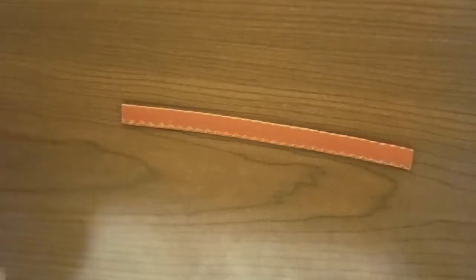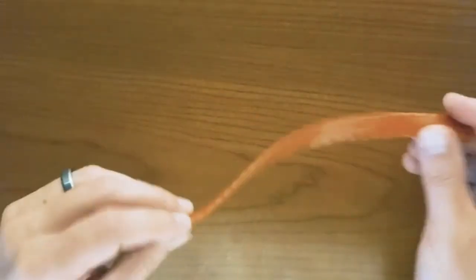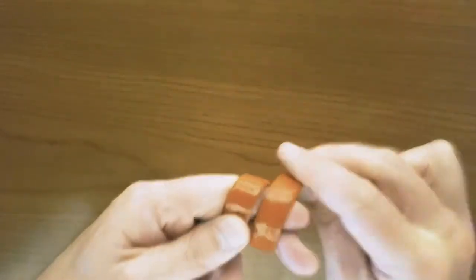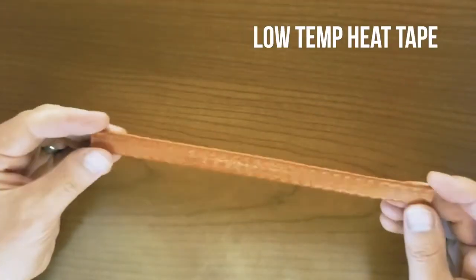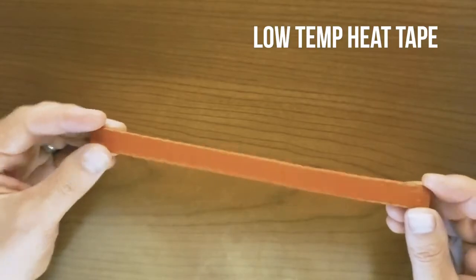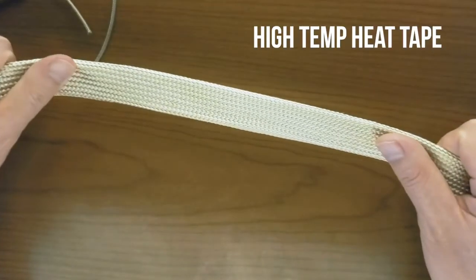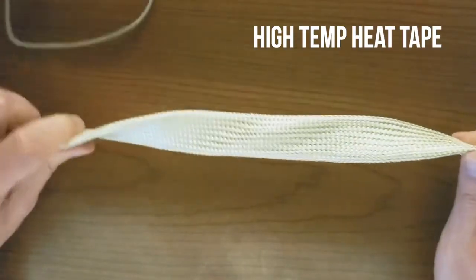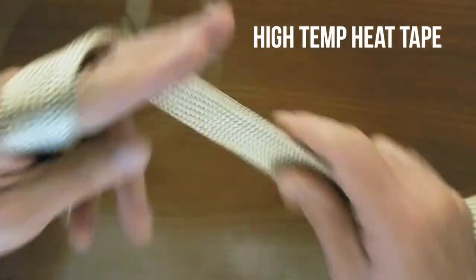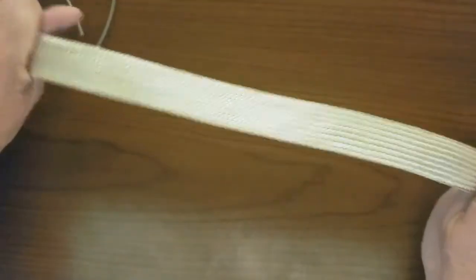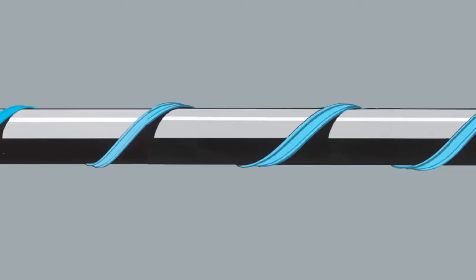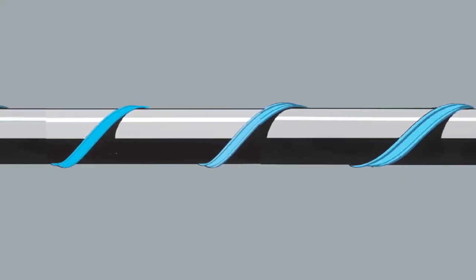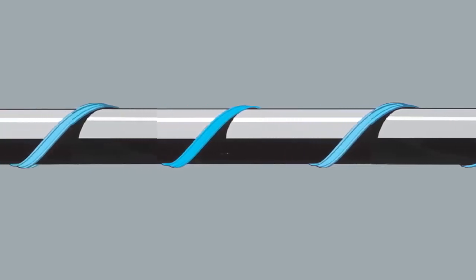Heat tape is a constant wattage resistive product that creates heat and is mainly used on small diameter pipes. Here's an example. It's small and thin and has two main varieties, the silicone one, which is used in low temperature applications below 400 degrees Fahrenheit, and the higher temperature fiberglass tape, which can be used up to 1400 degrees Fahrenheit. Heat tape products are not typically used for residential applications due to the high temperatures they generate. However, they can technically be used anywhere it's necessary to heat a pipe. They're popular in research and development and laboratory testing environments.